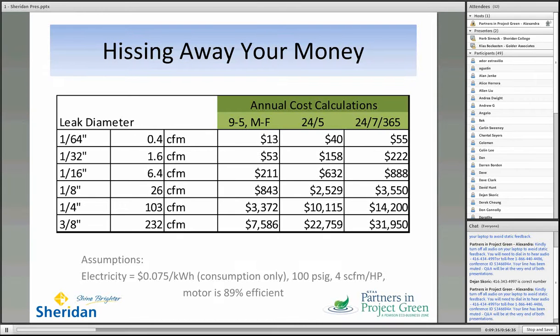In this chart, I'm just trying to highlight what it actually costs you to feed leaks. The nasty part of an air leak is it's not messy like water, steam, or hydraulic oil leaks. You see those, you see a puddle, you go and fix them. And the air leak you may not pick up on. And so it's easily ignored what that costs to you. Just as a note on this to help you follow, the leak diameter on the left gives you an indication of the size of the opening. And it's not a hole, per se.